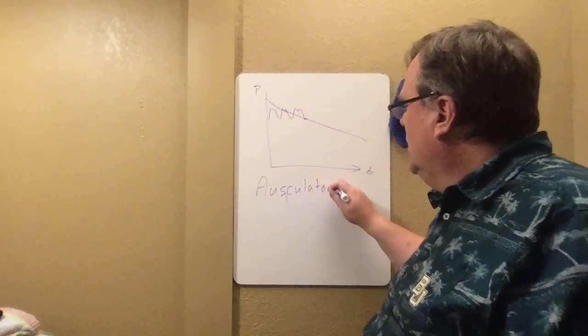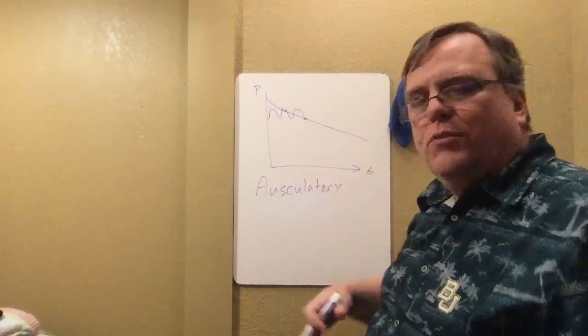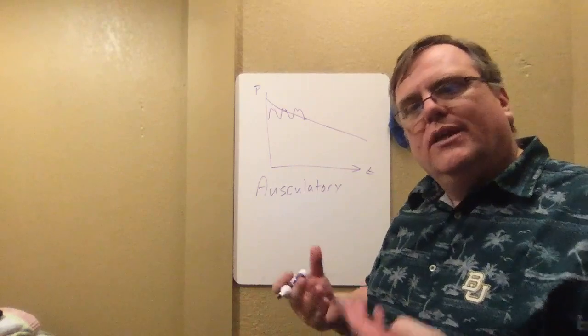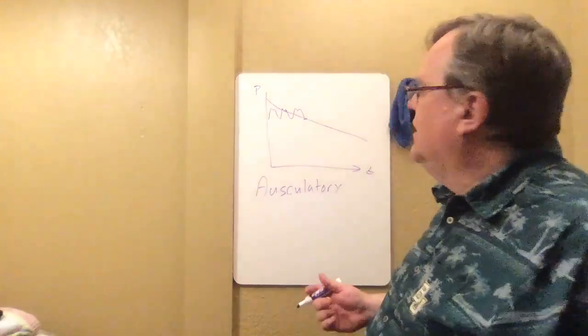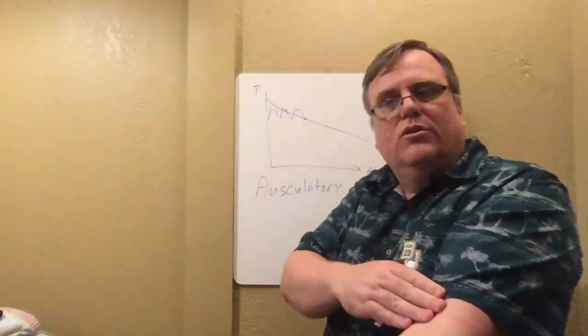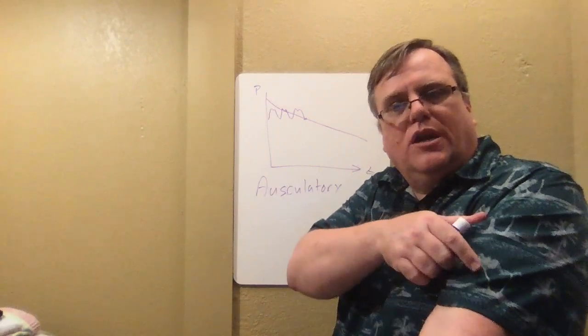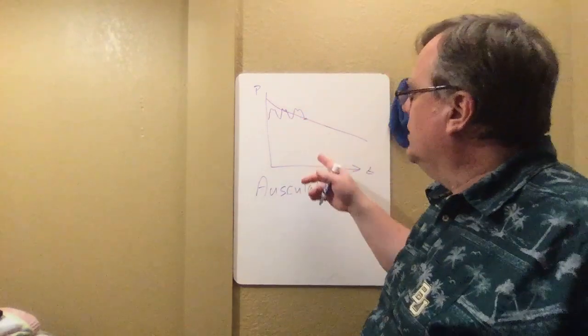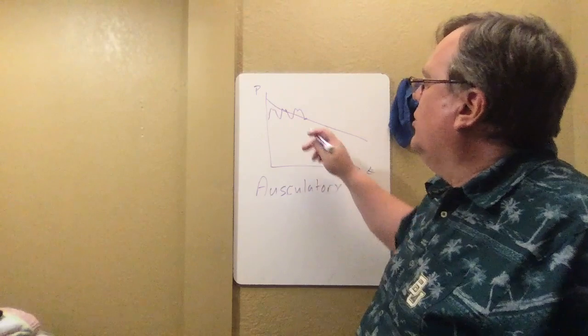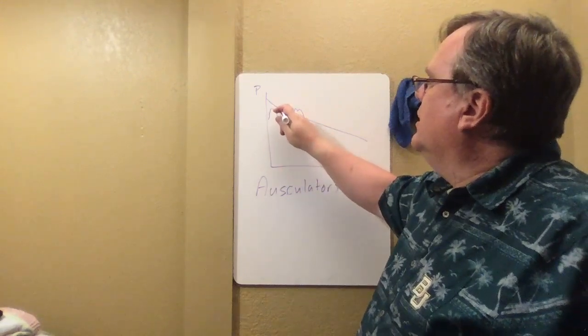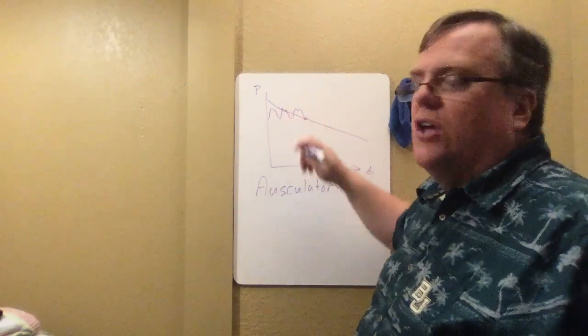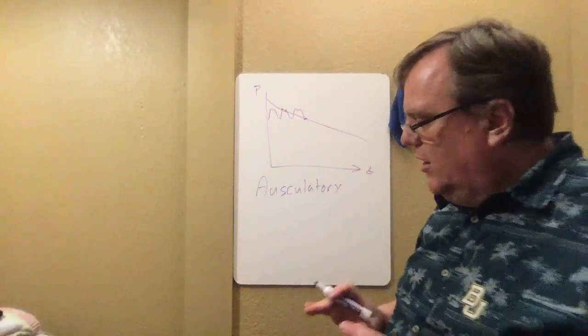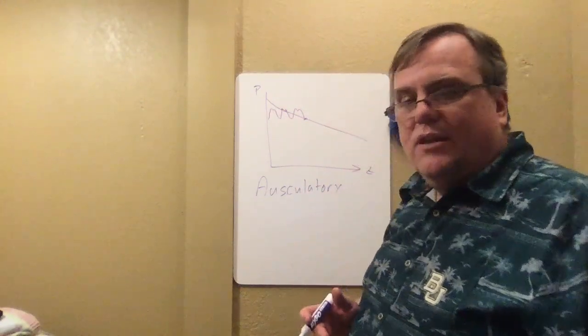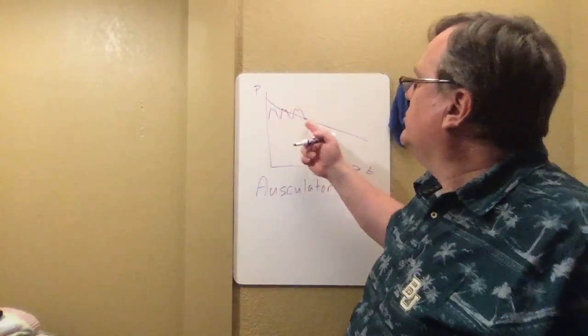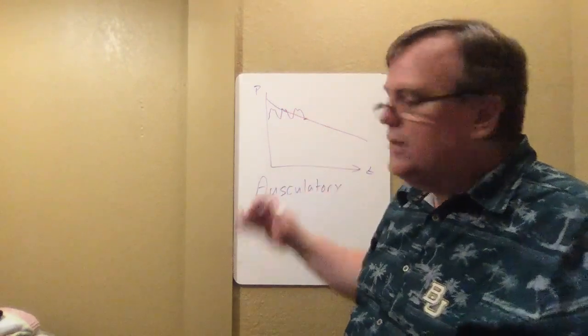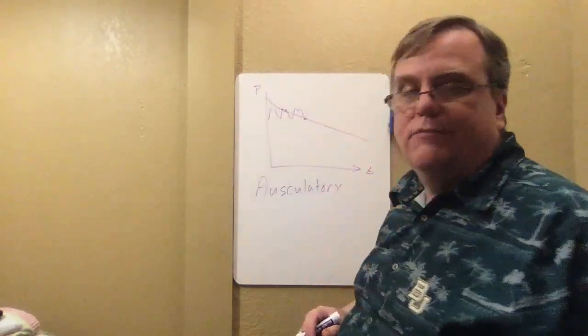Auscultatory technique. It's from the Latin word to listen, right? So this is kind of the listening technique. They put the listening device here just below the cuff, and they just listen to those sounds when it comes through. And all you're doing is picking the systolic and the diastolic pressure. That's why systolic is always the bigger number, because it's when it starts and when it ends, so it has to be bigger because the cuff is constantly decreasing.